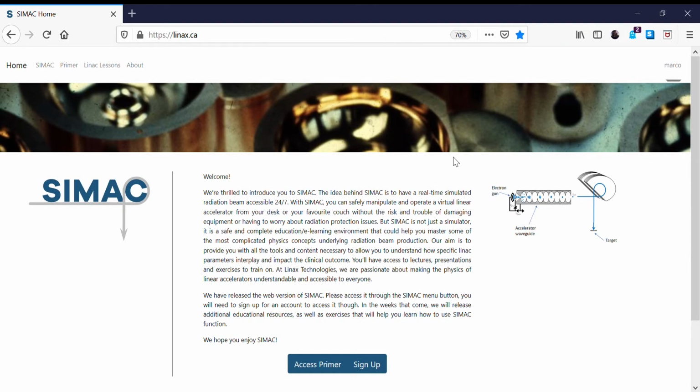In this video, we're going to pick up from where we left off last time, where we adjusted the RF driver power, and we saw that because the RF driver was going beyond saturation, an increase in the RF driver power to the klystron caused a decrease in RF power coming from the klystron to the accelerator, which caused a decrease in beam energy, which then caused a change in dose rate.